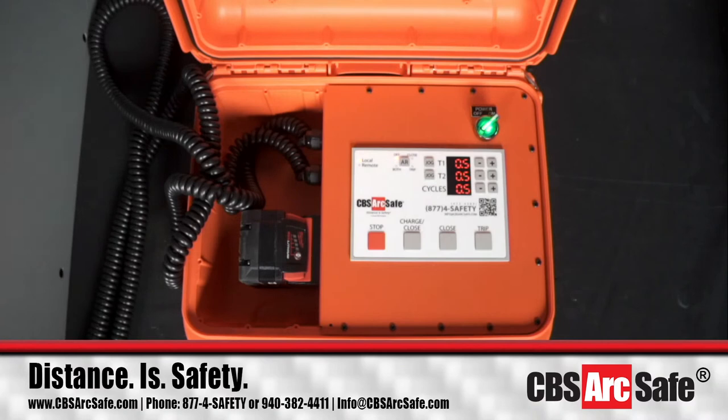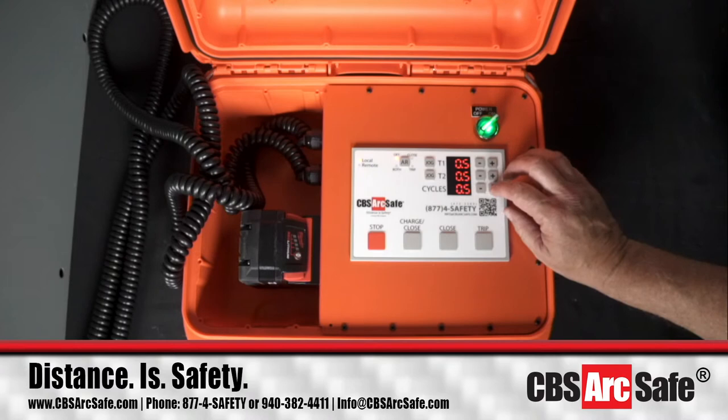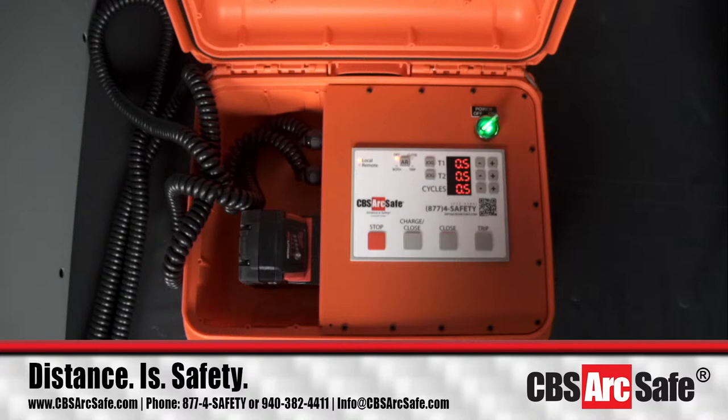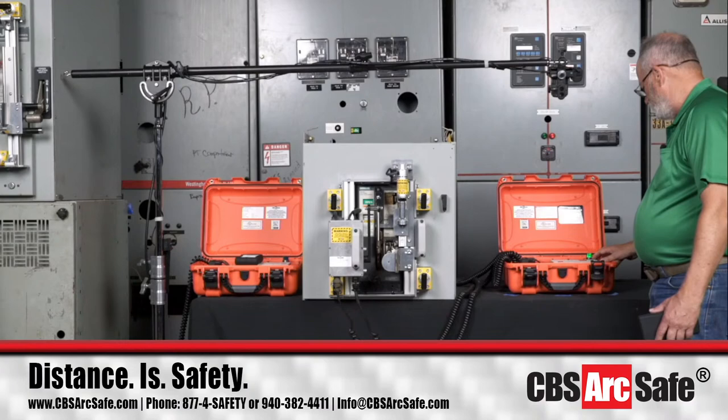Our label says we have to set 8 and 8, or one cycle, and T1, T2 at 8. So one cycle means one stroke, and then 8 means seconds that it's going to run. T1 and T2 tell the timer on the motor how long it's got to run in each direction for complete travel. We do work to put travel stops on the motors on most applications so that if we have something where we have a hard physical limit, we're not going to damage the switch here. So let's now set this to 8.